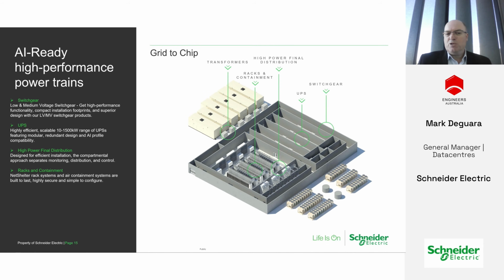High power final distribution. That is where we're really seeing a change. 40 kilowatt racks, okay, we could have a power rail, 60 amps a phase, 100 amps a phase. Now we're talking maybe 1,000 amps and beyond, 1,000 amps per phase. So what does that look like in terms of a power rail? Is there even a power rail available today for that? Certainly at 1,000 amps a phase, no. Busway is available, but certainly at a rack level, 1,000 amps a phase is being used with multiple power rails. So you'll have 3 or 4 power rails into the rack. The other really interesting is racks and containment.